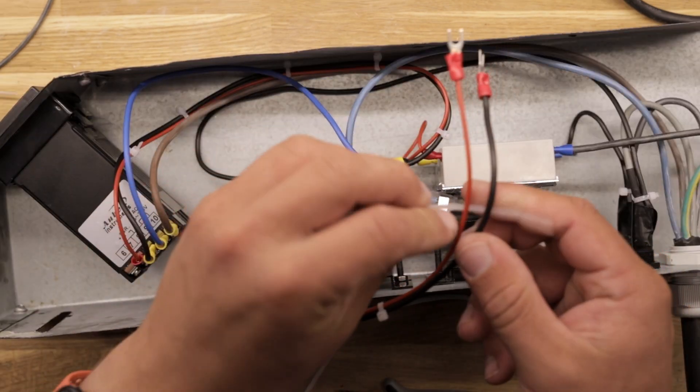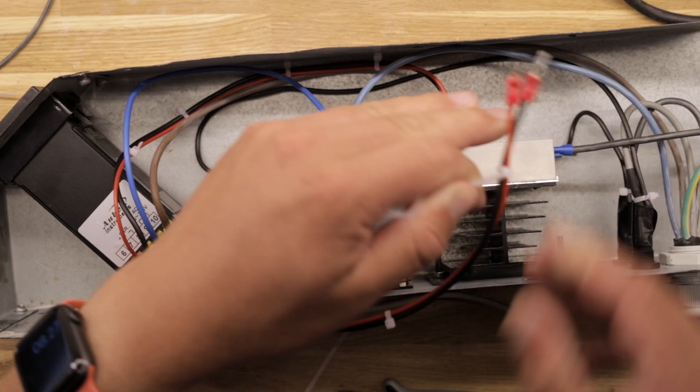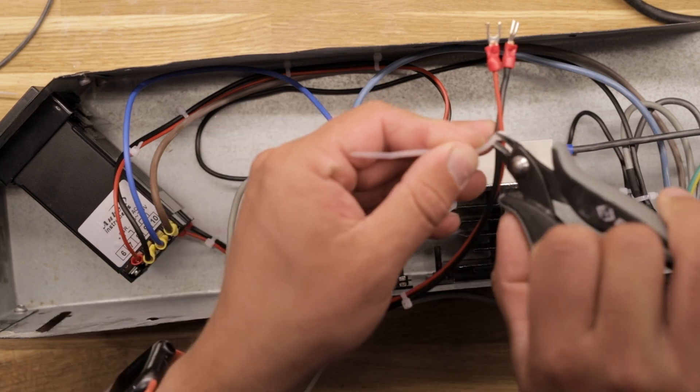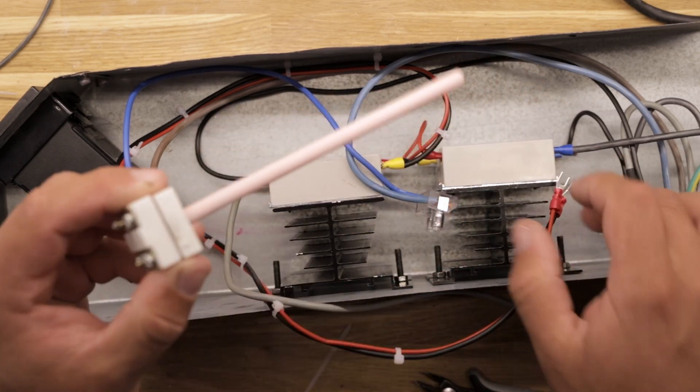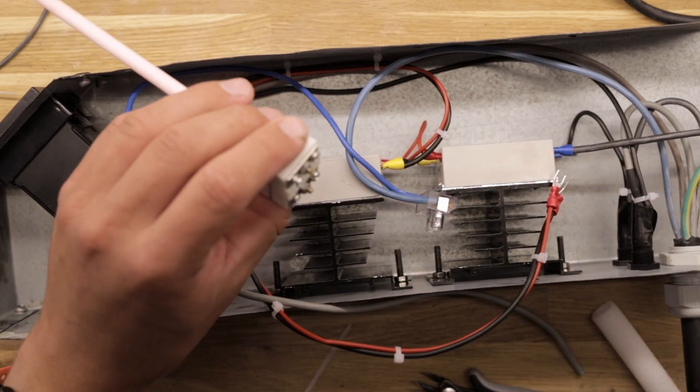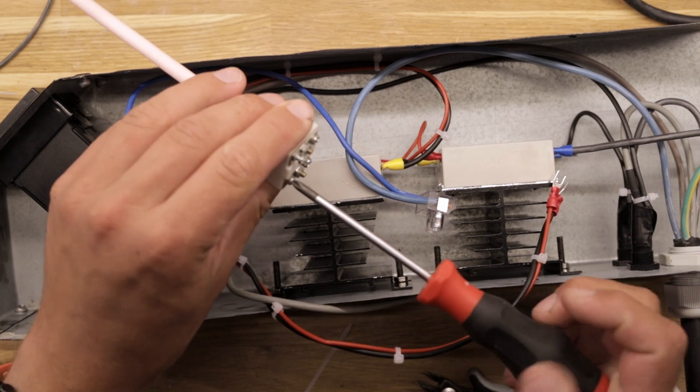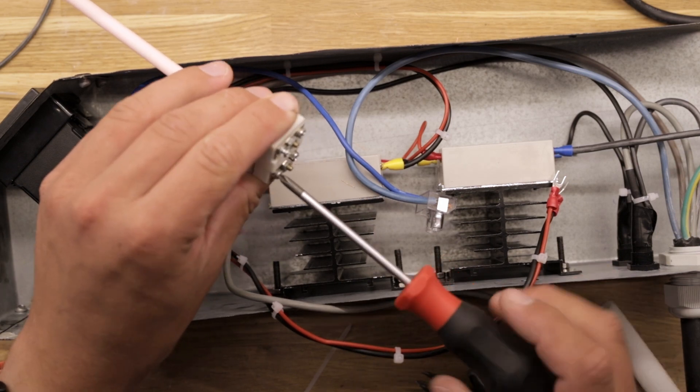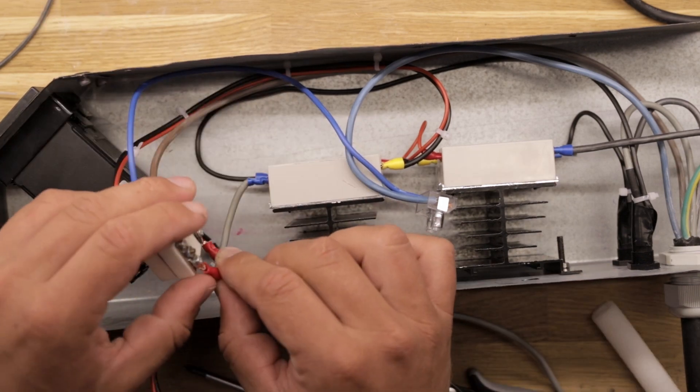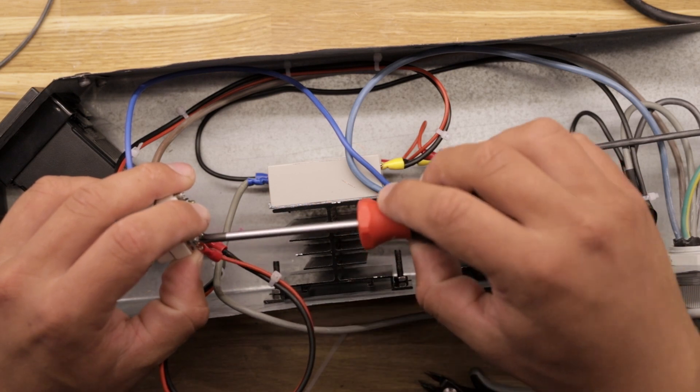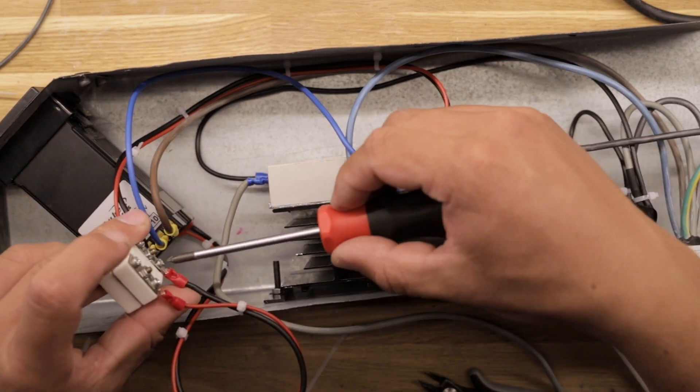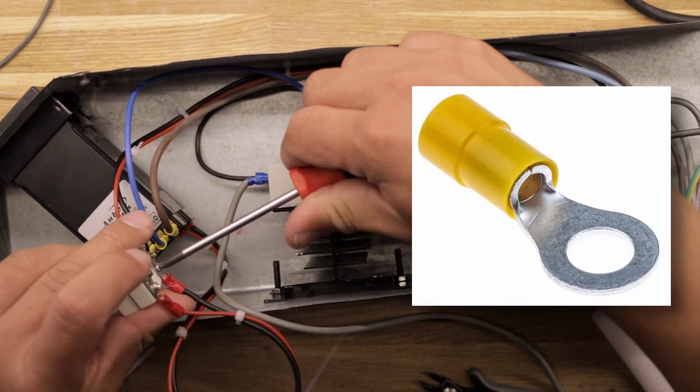As the next step, I will tie up the thermocouple wires with an extra cable tie and connect the thermocouple itself. Initially I have used these fork type cable lugs, which I later figured did not connect well. So these should rather be ring type to get a more secure connection, as seen on this image.